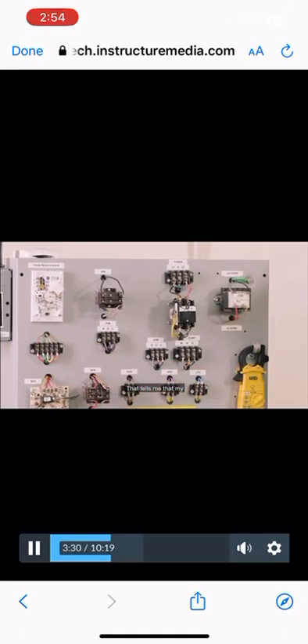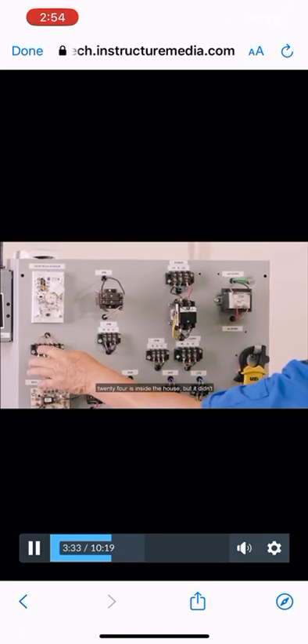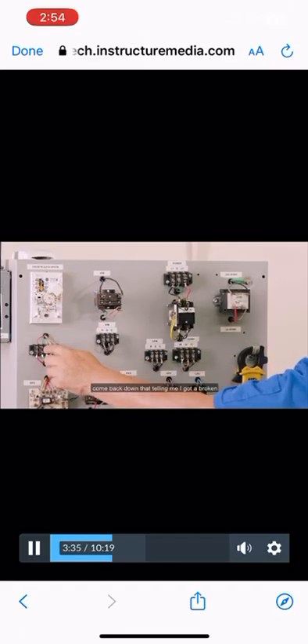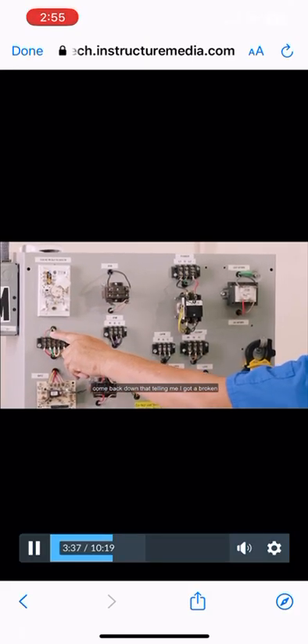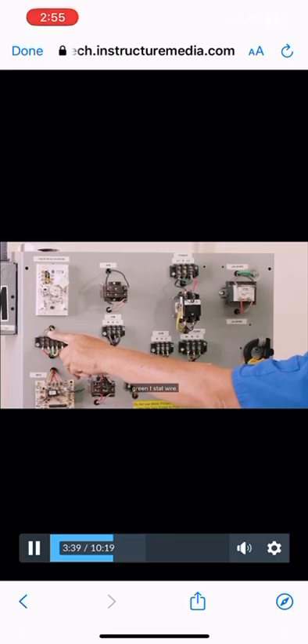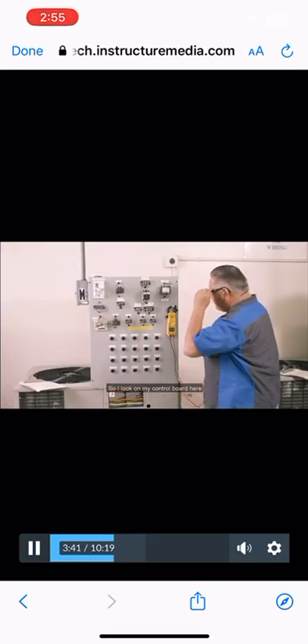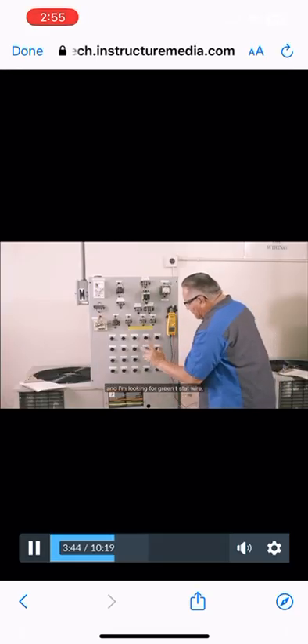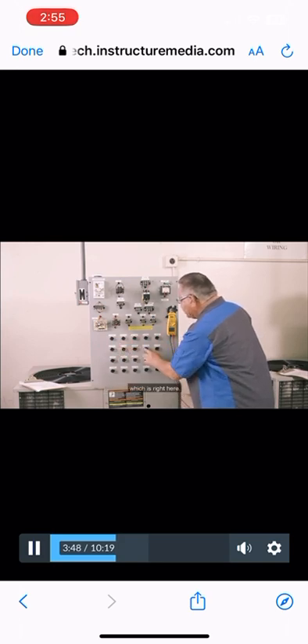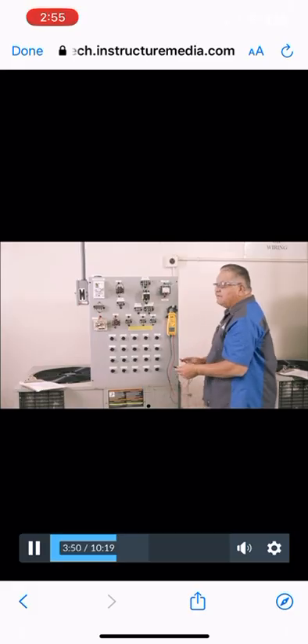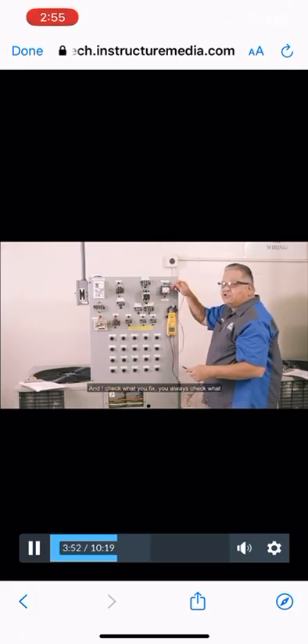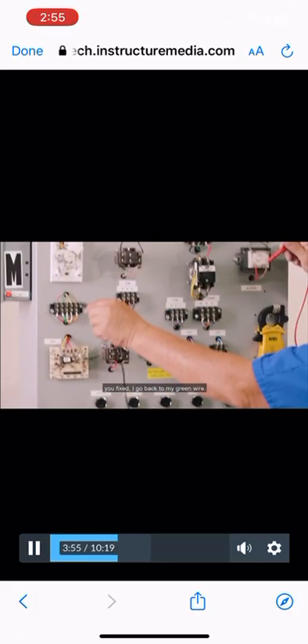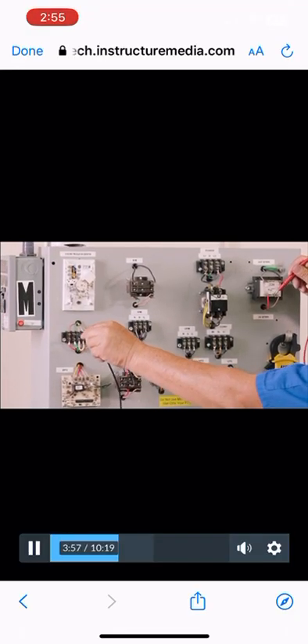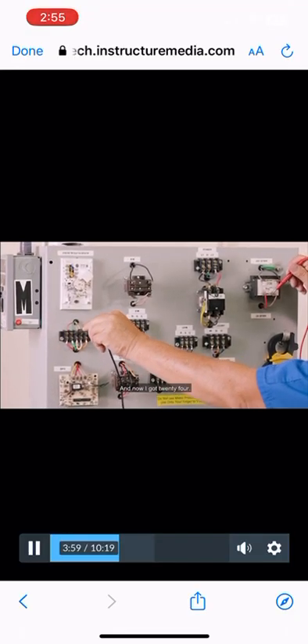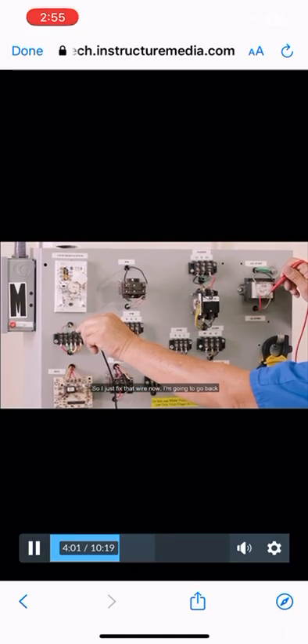That tells me that my 24 is inside the house, but it didn't come back down. That tells me I got a broken green T-stat wire. So I look on my control board here, and I'm looking for the green T-stat wire, which is right here. I push it, and I check what I fix. You always check what you fix. I go back to my green wire, and now I got 24. So I just fixed that wire.